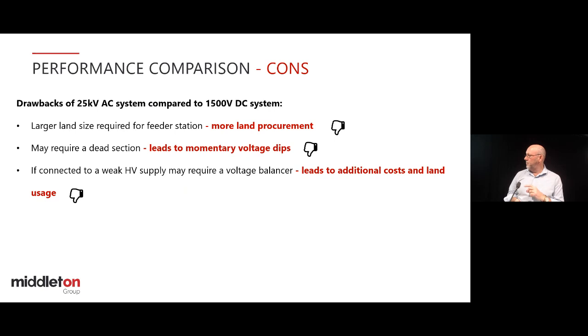So it is a negative in the sense of traditional 25 kV AC power supply connection, but SFC allows that connection to be done at a lot lower voltage. Reasons for that are mainly load balancing. It's a balanced 3-phase supply. And as you saw on the previous slides, you can run SFCs in parallel like a DC railway, with lots of in-feed points, so they can be smaller capacity each.